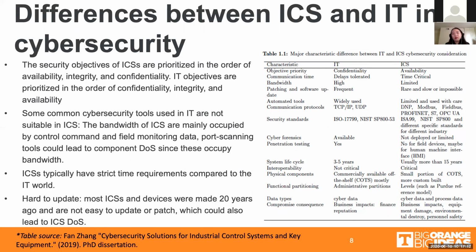And also some of the common security tools used in IT are not suitable in ICS, because the ICS bandwidth is mainly occupied by control commands and the field monitoring data. So the port scanning tool, which is a very common tool in the IT world, cannot be used in most ICS, because it could even lead to component DOS, since it occupies bandwidth as well. And ICS typically have very strict time requirements compared to the IT world. So the cybersecurity measures you deploy can't disrupt these time requirements.